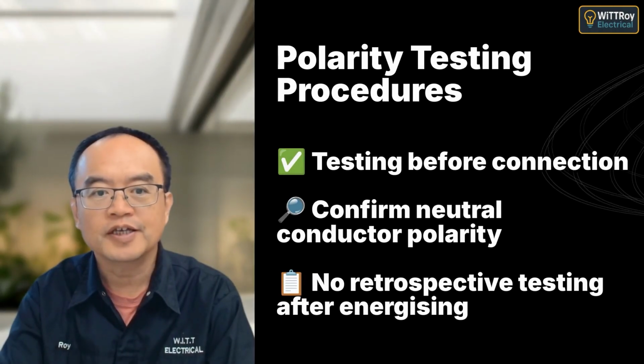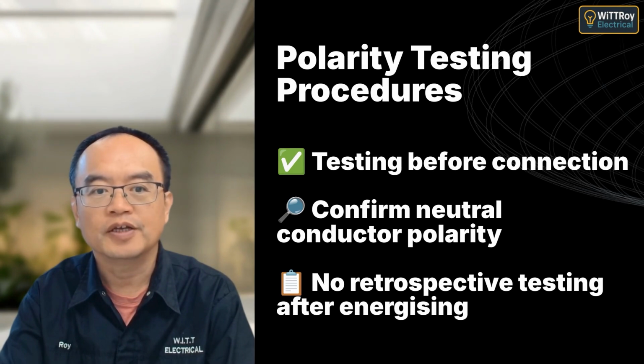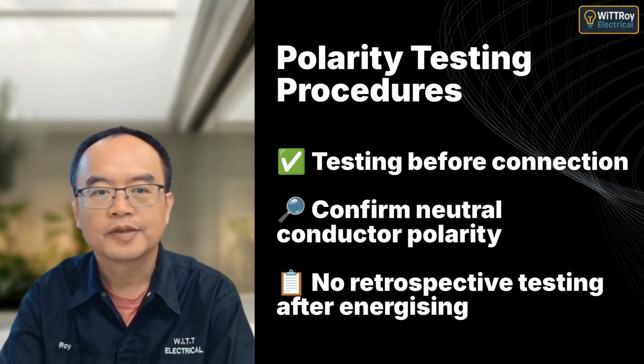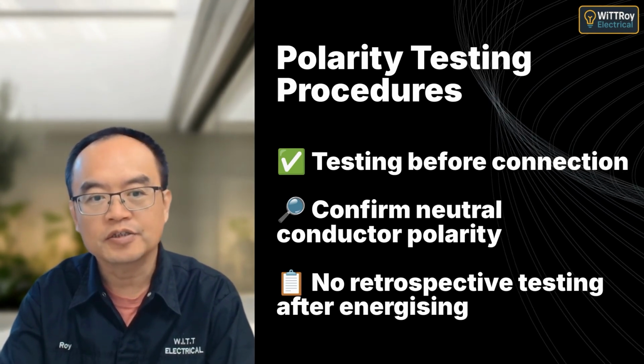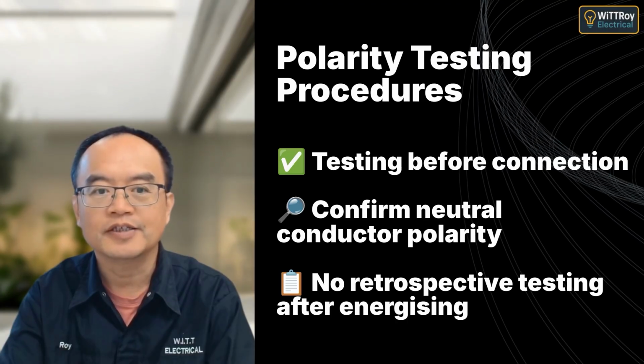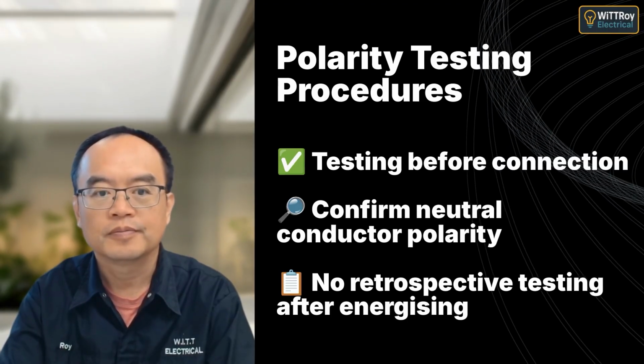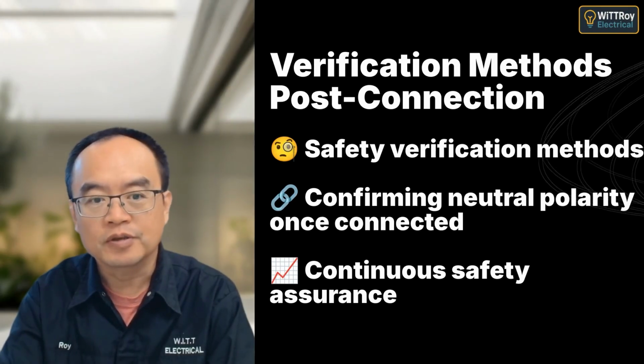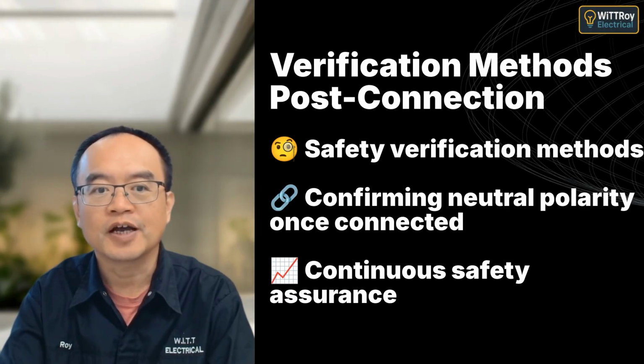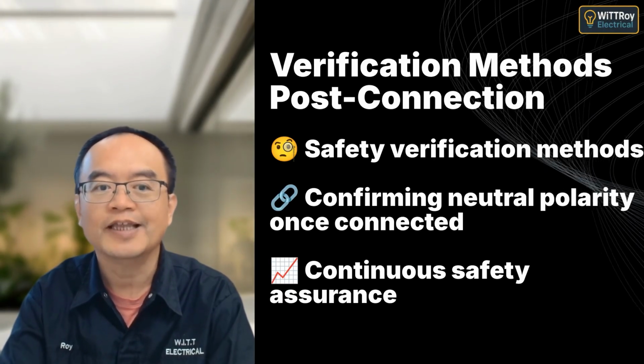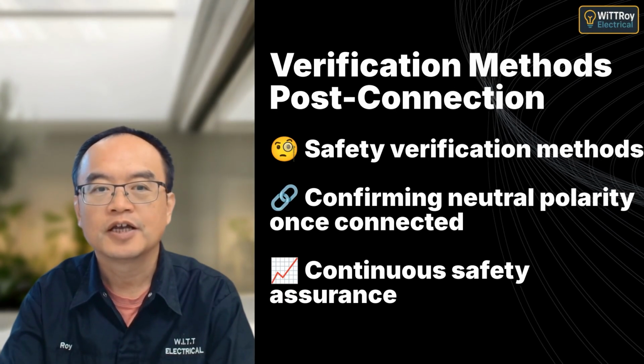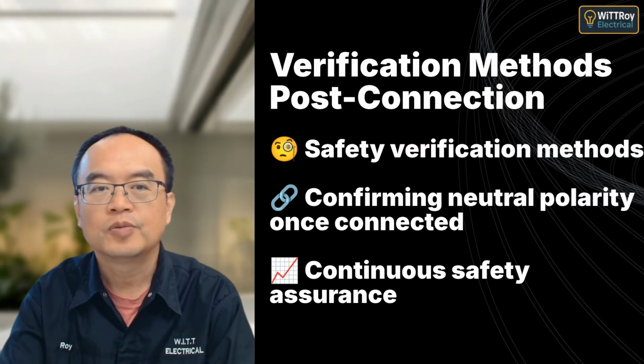Before an installation is connected, polarity tests must positively identify the neutral conductor. Remember, testing must occur before energizing. Retrospective polarity testing isn't allowed. Safety verification methods are vital for identifying correct polarity even after connections are made. Consistent checking ensures installations remain safe over time.